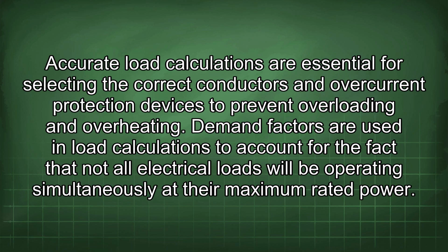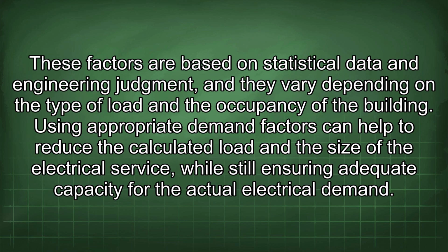Demand factors are used in load calculations to account for the fact that not all electrical loads will be operating simultaneously at the maximum rated power. These factors are based on statistical data and engineering judgment, and they vary depending on the type of load and the occupancy of the building. Using appropriate demand factors can help to reduce the calculated load and the size of the electrical service, while still ensuring adequate capacity for the actual electrical demand.